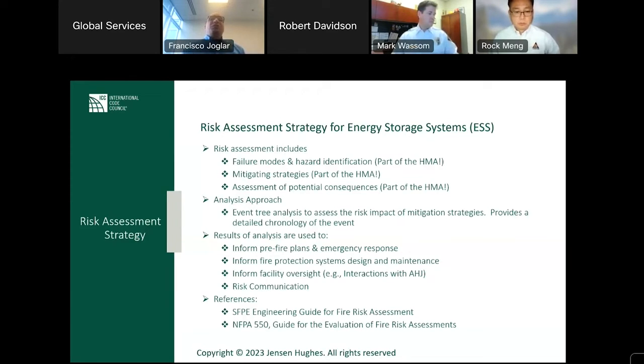so that we see the chronology of the event, and in each step of that chronology of the event, we can identify what are the mitigations for the different events that can happen in the chronology, and what if those mitigations fail or they are not operating in time. Okay? And these results from the HMA, they inform pre-fire plans, they inform emergency response, you improve your procedures, you increase the facility oversight, and you can communicate risk. So they have a lot of benefits if you document this as required in the code. Next slide, please.